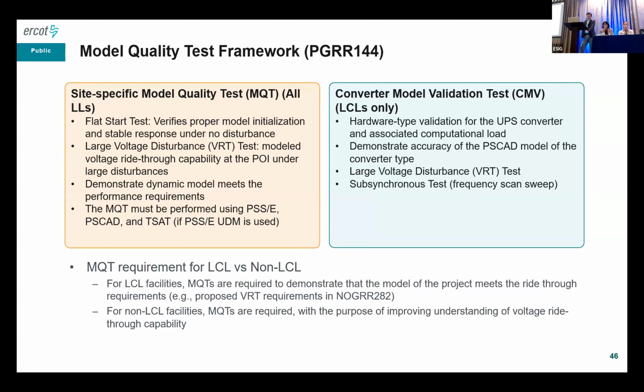The converter model validation test is only for large computational loads, so data centers and crypto mining load. It's a hardware benchmarking test to ensure the PSCAD model of the converters matches the actual response from the actual hardware converters. It has two tests: the large voltage disturbance test, which I mentioned earlier, and a subsynchronous test. The subsynchronous test is about performing a frequency scan sweep to make sure that the PSCAD model of the converter is in good shape, not only for nominal frequency, but also for other ranges of frequencies.